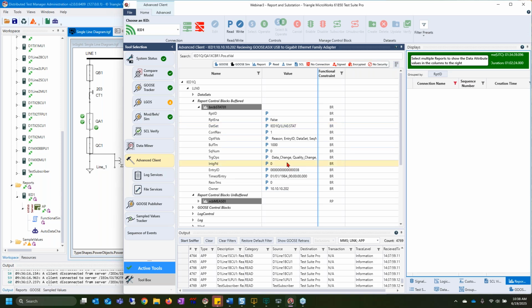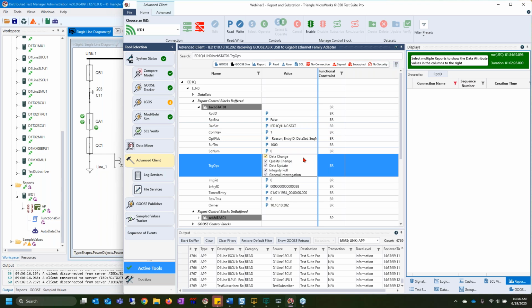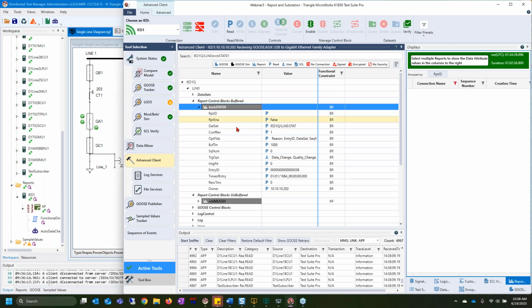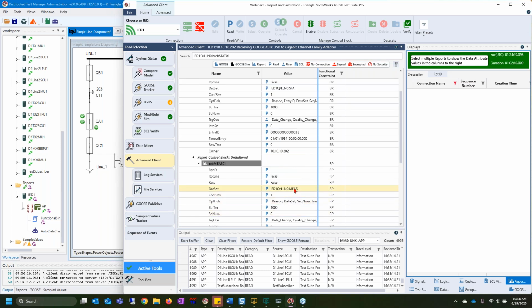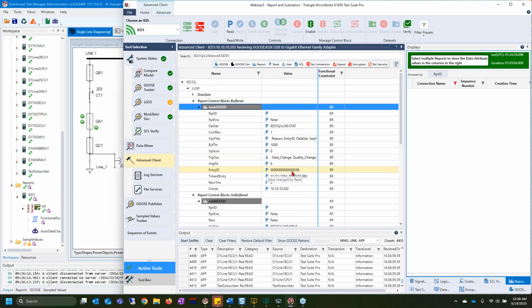As mentioned previously, we do have different trigger options for this. So we've just set everything for this specific data set here on data change, quality change, data update, integrity poll, general interrogation. And likewise, we have the measurement values coming in at the measurements. Typically, when you're getting analog values, it would make more sense for historical data to not be as important, which is why you can do some deadbanding, or you can set up different ranges or whatnot. I went ahead and put this as unbuffered just because I want to know when it changes, but historically I'm not too worried about that.